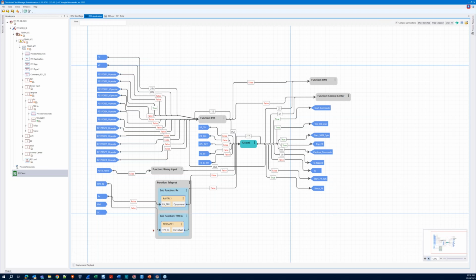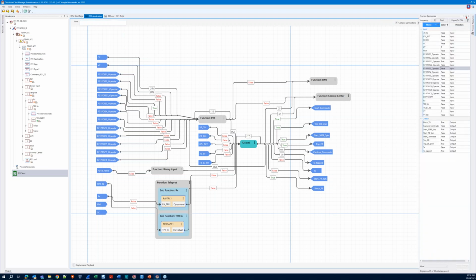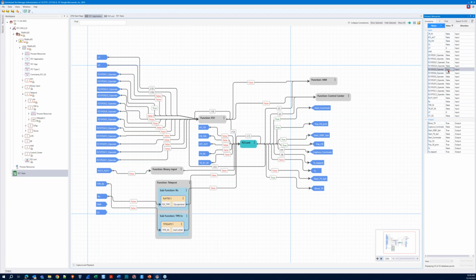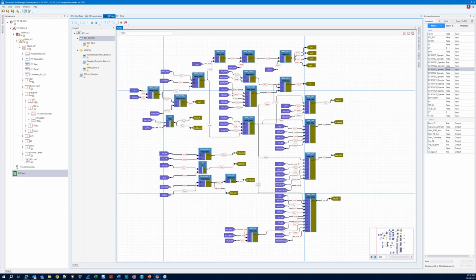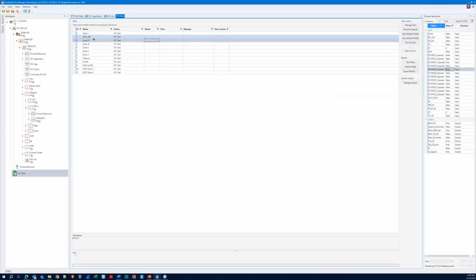Now, because it can become tedious to test complex schemes repeatedly, especially as I'm making changes, there's also the opportunity to use the test sequencer. It does kind of a similar thing to what I did here, where I selected a specific input and set a value for it, but instead it defines values for every one of these inputs and expected values for every one of these outputs. Effectively, it sets the values for these inputs, waits a short period of time, and then monitors to make sure that these outputs are correctly set. It's done using a table interface.